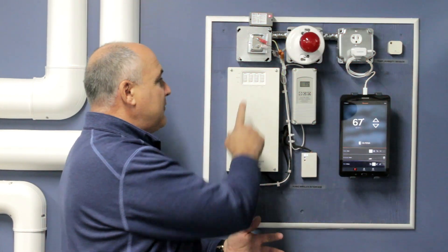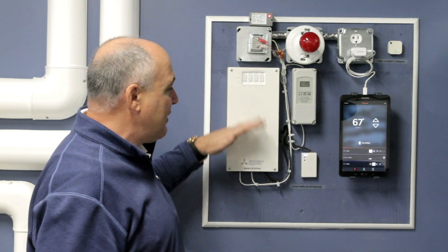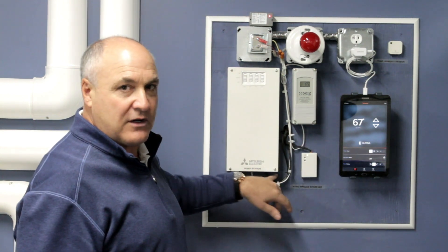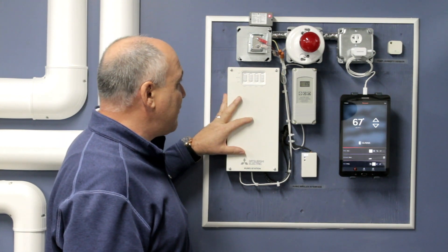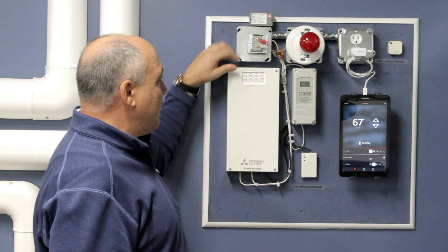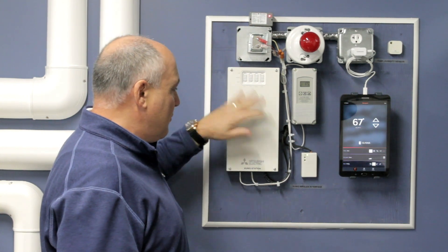Above the temperature, the air source heat pump comes on. I'm switching it on and off, but it would be doing it from a sensor that goes outside. There is an outdoor air temperature sensor that ties into the Kumo Cloud station. You do have to run 24 volts to it — a little transformer, a little 110-volt step-down — goes right into it and powers it up.